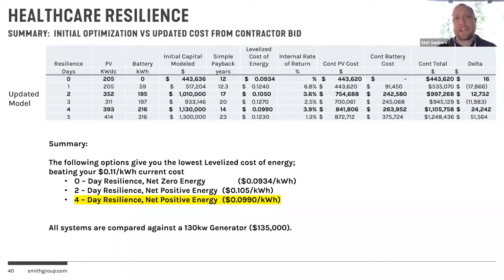But what we were able to do is put in their energy loads. We did a whole series of resilience scenarios. How many days of outage do you want to prepare for? And the sweet spot for them came out to about 4 days of backup. And remember, it's not that your battery is sized to operate for just 4 days, because you've got on-site generation. In this case it was PV, but you could pair that with a generator as well. PV helps charge the batteries during the day. And weather is in here. You can analyze for cloudy weather, et cetera. We can take all of that into account.